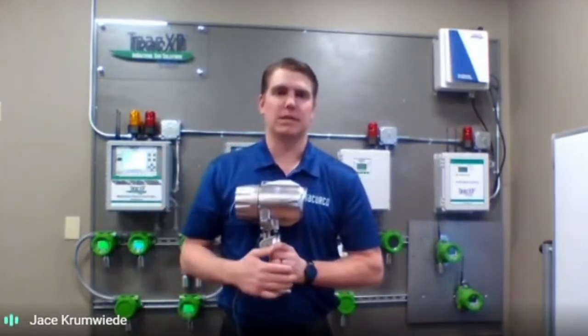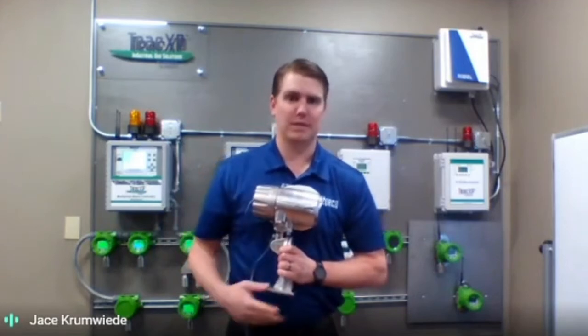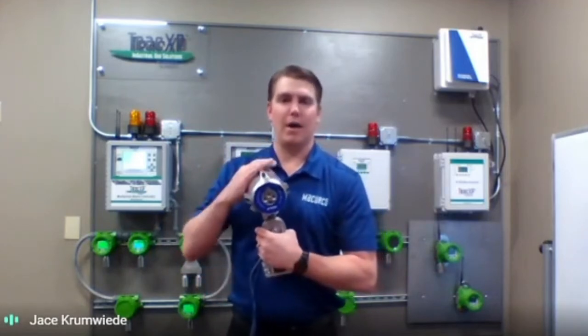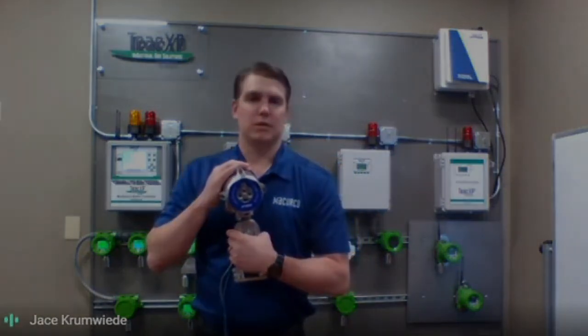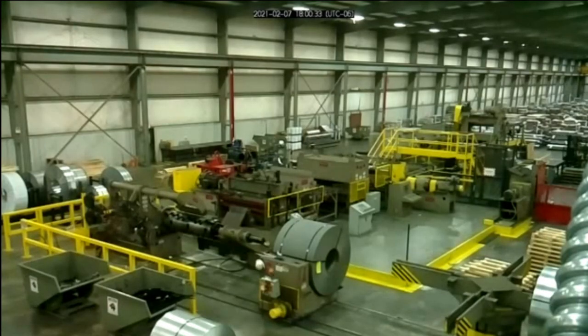Very nice. The last item, the IR cameras, as you refer to them, flame detection. So a lot of times with gas detection, you are going to be worried about the flame and how it propagates. We have both UV-IR and IR3 or triple IR. We do have options with or without an HD camera. That camera is going to allow you to not only get real-time visibility of what it's seeing, but it can store that log minutes before and minutes after, so you can go back and find out what happened, what started that fire, as well as after the fact, what sort of fire suppression, how did that handle getting rid of the fire, whether it's CO2 or foam.